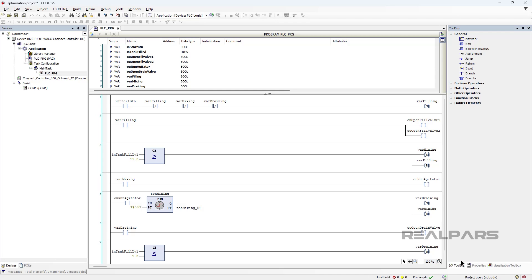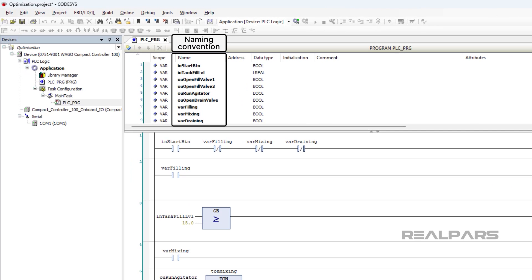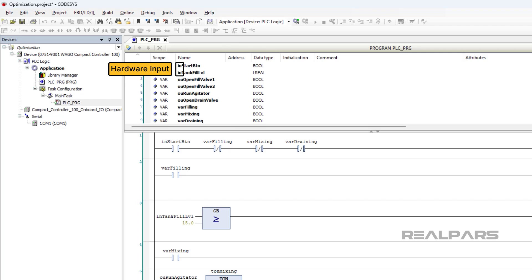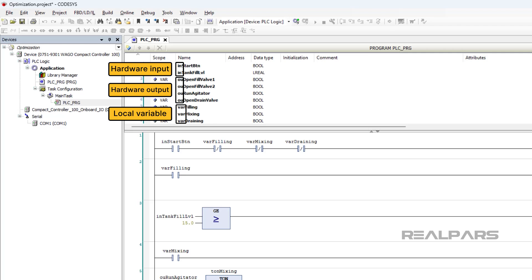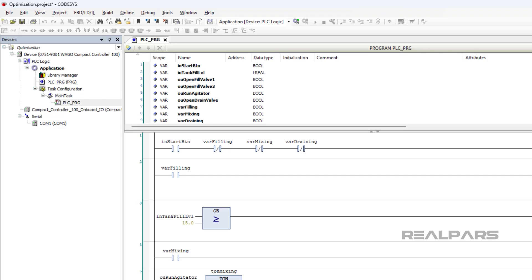In general, you should use a naming convention to name all of your variables to ensure that variable names are consistent throughout your projects. In this example, I use the prefix IN to indicate a variable as a hardware input, OU to indicate that a variable is a hardware output, and VAR to indicate that a variable is a local variable.